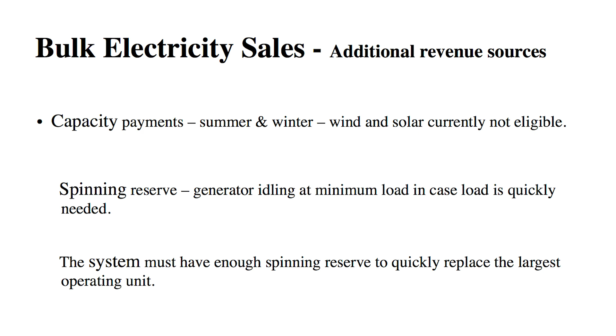So capacity payments, there's other ways for them to make power. I'll go quick. Spinning reserve is basically I'm idling in case a big unit goes down, I can come up and replace it real quick. We do that a lot with combined cycle. And the system must have enough spinning reserve to replace the largest unit that's online. So if that's a 1,000 megawatt unit, I've got 1,000 megawatts that we're all paying for as spinning reserve in case that unit crashes, so we can quickly come up and replace that.